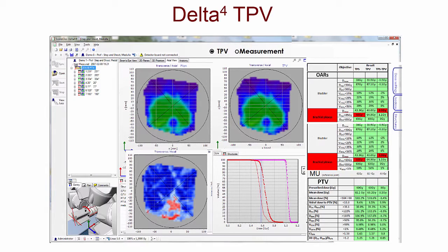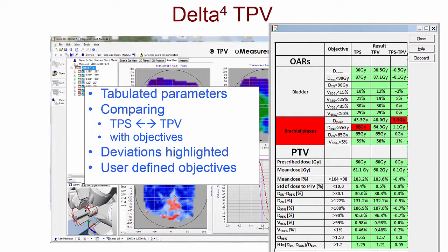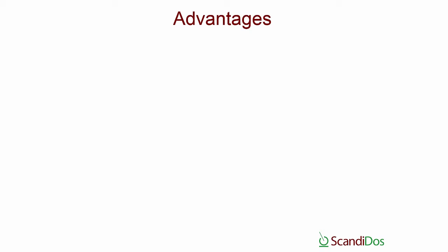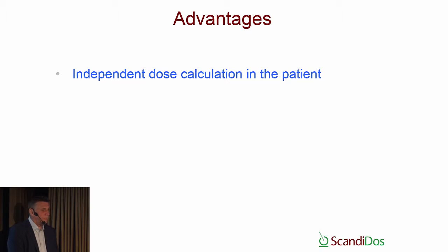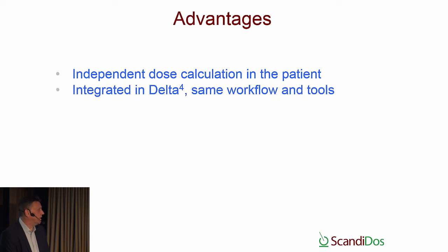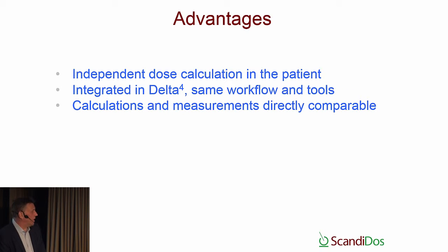It also has the tables here with the tabulated parameters comparing treatment planning system and the treatment planning verification with a number of objectives. And you can set up the criteria due to a standard, or you can define your own criteria if you want to. So the advantage of having the treatment planning verification in the Delta4 system is, of course, first of all, independent dose calculation in the patient, but it's also really nice that it's integrated with the Delta4 system. And it brings you the same workflow and tools as for measurements. And calculation and measurements are directly comparable.